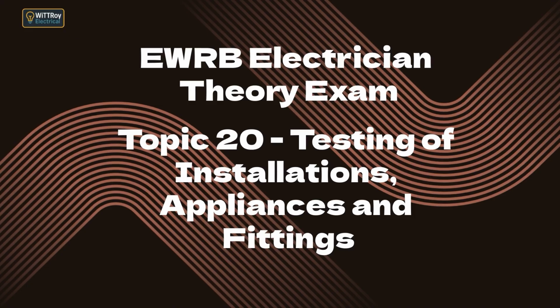Topic 20g. State that all the tests of installation wiring work as detailed under Regulation 65 and certification for compliance Regulation 66 to 69 must be completed before connection to a power supply. Regulations 65 to 69 require all testing and all certification to be completed before connecting an installation to supply. The electrician must complete all mandatory tests, complete the visual inspection, complete the Certificate of Compliance, COC, complete the Electrical Safety Certificate, ESC, and only then connect the supply.